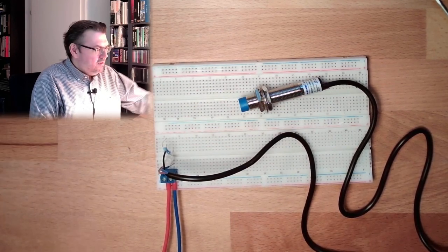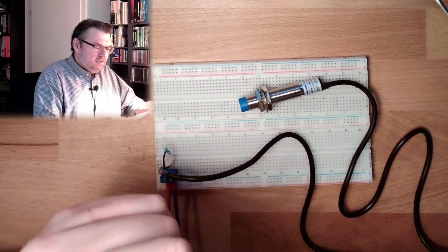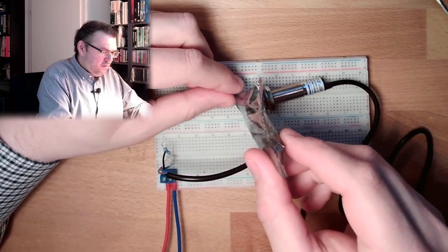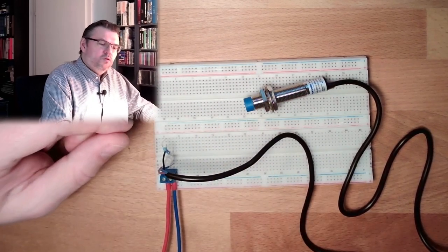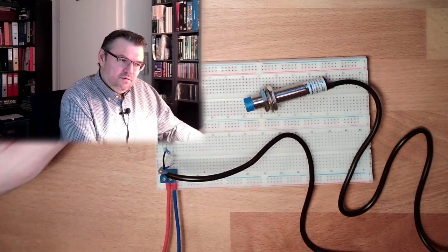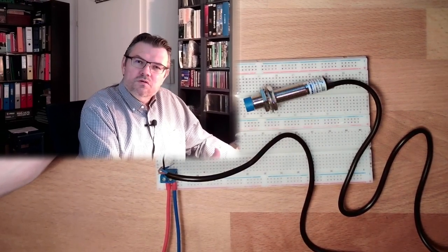The reason is that it is detecting metal. So see, this is plastic bag, not detected. This bag is some metal, but it's too less metal. This is metal, detected very good. So an inductive proximity switch is detecting metal. Nothing else. How good or not good depends on what metal type this is. The reference is always an iron plate. So we see how this looks like, how this is working. Now let's summarize those things up and see the working principle on a sheet of paper.